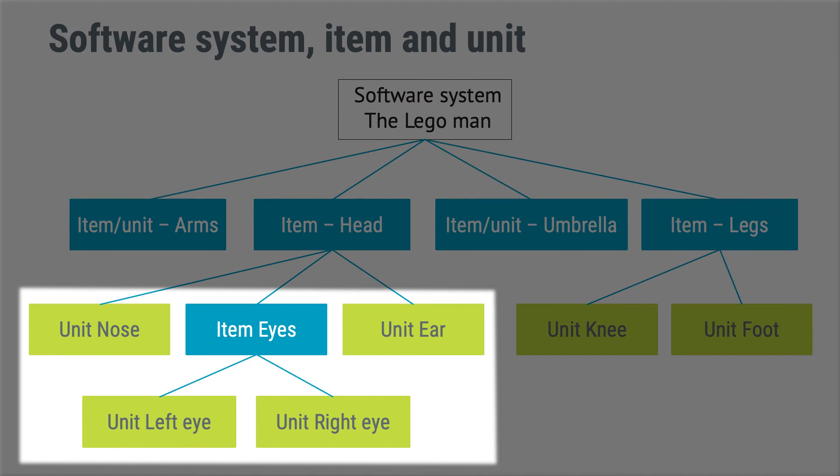Before we say goodbye to Mr. Lego, I want to highlight that you can mix items and units on the same level. Also, a widespread misunderstanding is that the term unit is equivalent to unit in unit testing, commonly used by software developers to test software. It is not. A software unit as defined by IEC 62304 can be tested with the help of multiple unit tests, and you can also verify items with the help of unit testing.